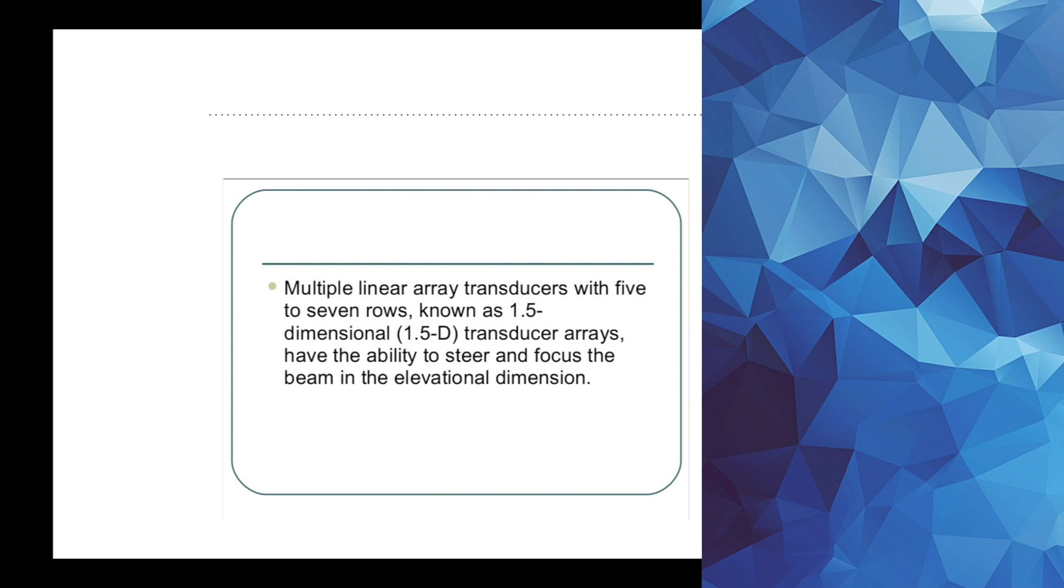But what we've recently realized is that if they use not only multiple columns of crystals but multiple rows of crystals, we can actually focus in the elevation direction as well. So that would be known as a 1.5D transducer.